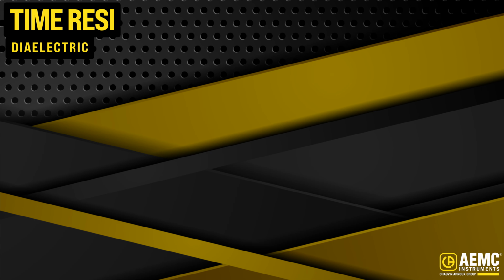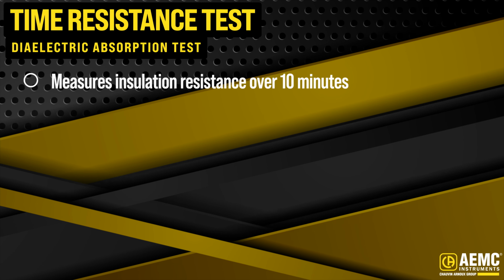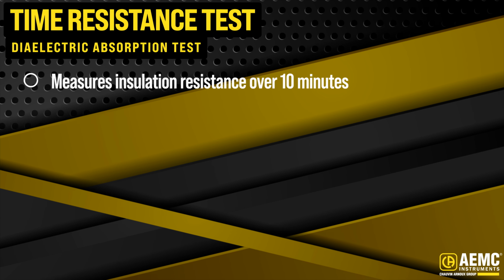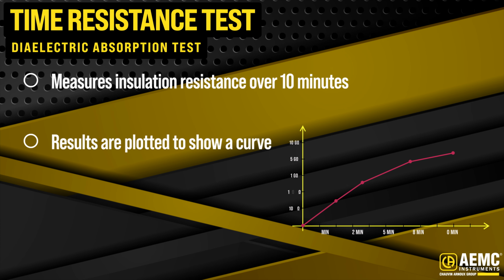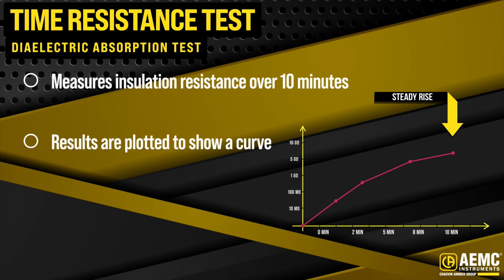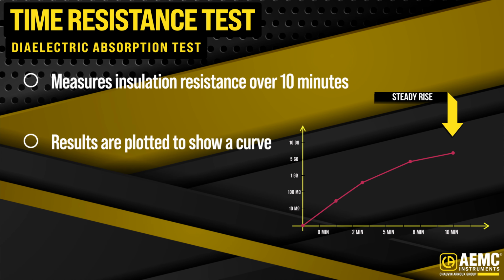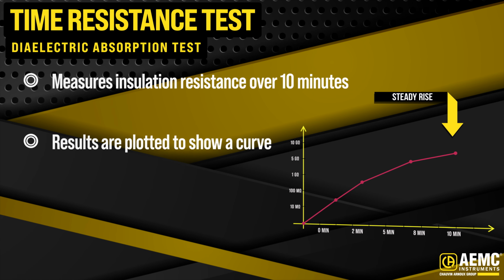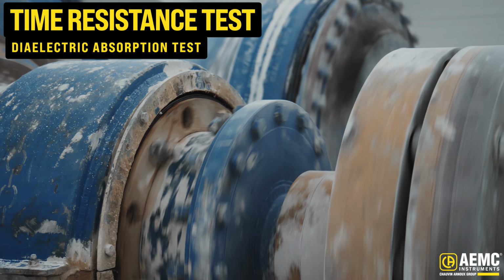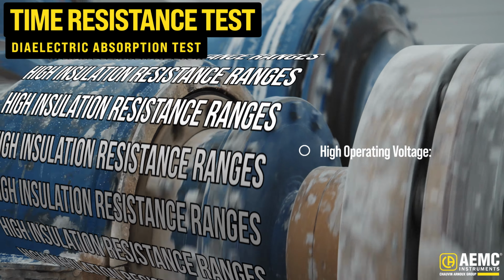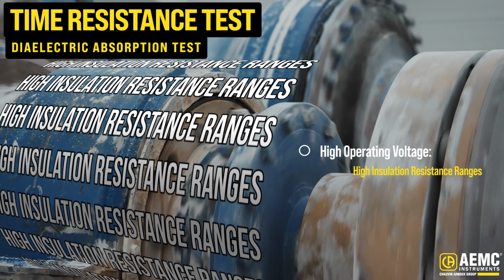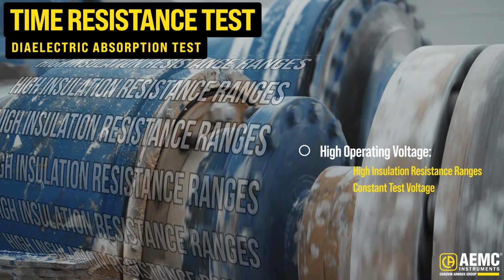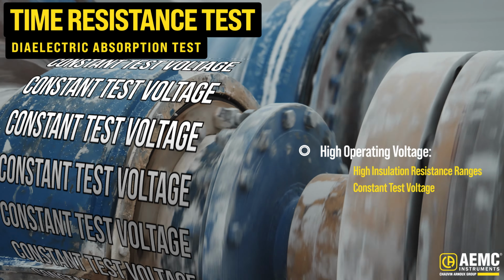The time resistance test, also called the dielectric absorption test, measures insulation resistance over 10 minutes. The results are plotted to show a curve that should rise steadily. Time resistance tests on large rotating electrical machinery, especially systems with high operating voltage, require high insulation resistance ranges and a very constant test voltage.